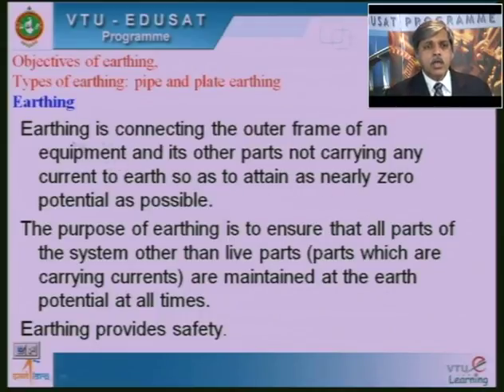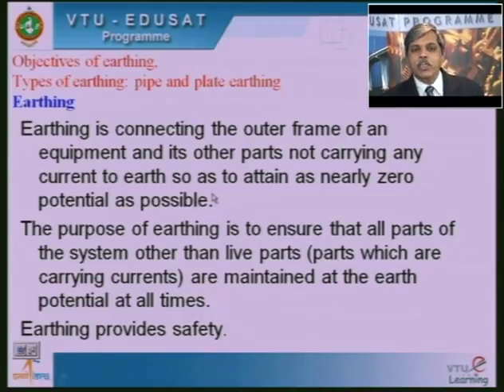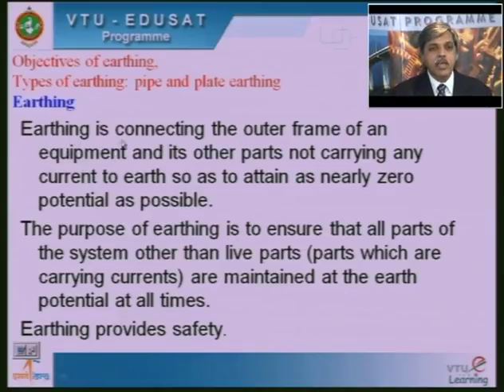Earthing is connecting the outer frame of an equipment and its other parts not carrying any current to earth, so as to attain as nearly zero potential as possible. In case these parts of the machine, the outer frame of the equipment and other parts, carry any current, by providing earthing, the current will directly flow to the ground. Even if any human being touches that part, he won't get the shock. So that is the main reason why we have to earth the equipment.